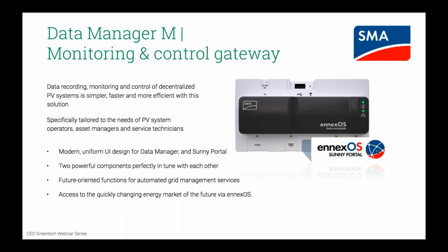The data manager has not only the smarts to collect data from the inverters, but also built-in software intelligence to implement local control capabilities like zero net export or reactive power control, if required for your project. The data manager then acts as your gateway to the World Wide Web, where information can be pushed up to our Sunny Portal monitoring platform, or, if preferred, a third-party monitoring platform, since we support industry standard communication protocols like SunSpec Modbus.